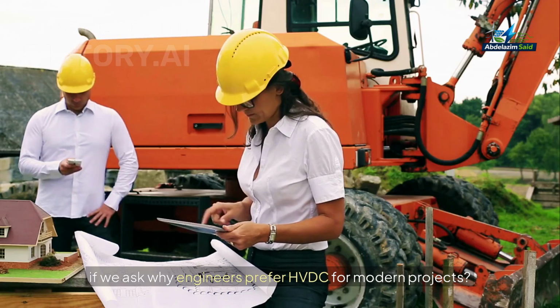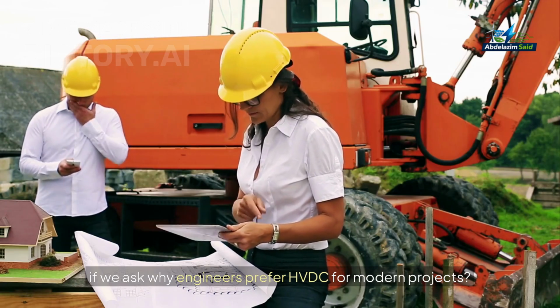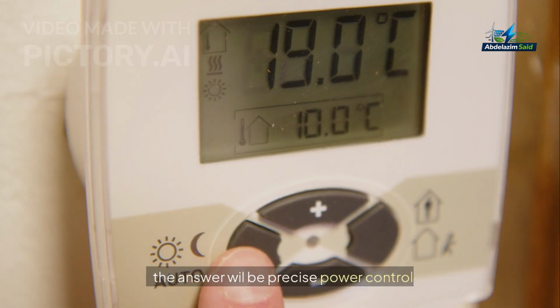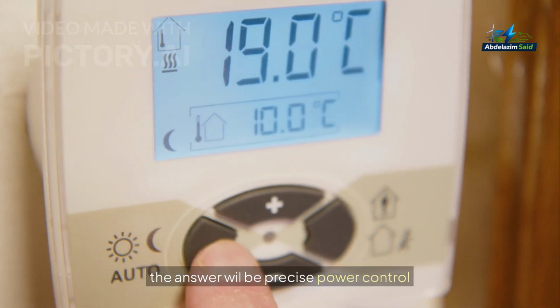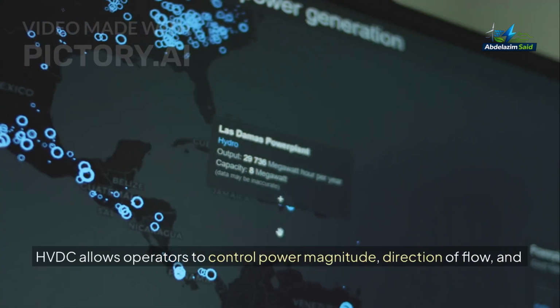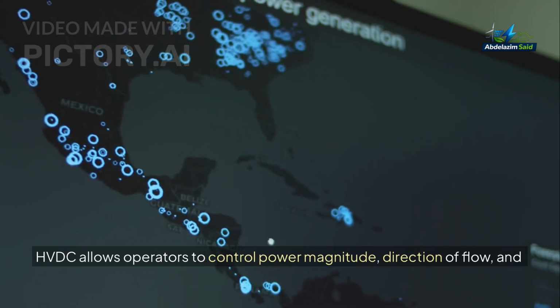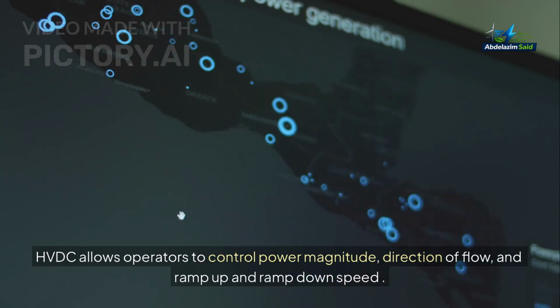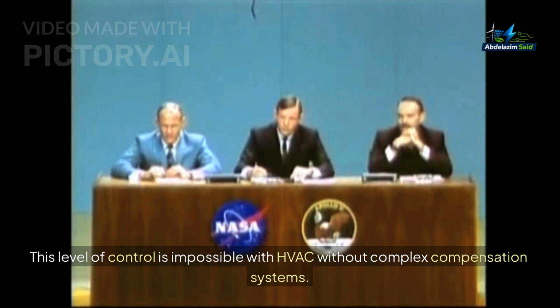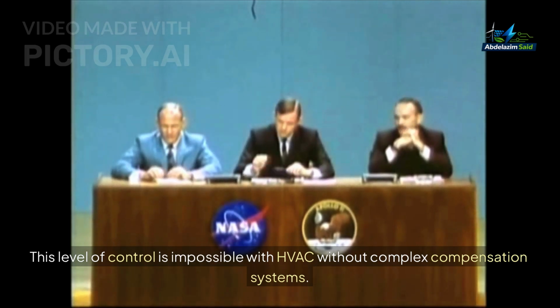If we ask why engineers prefer HVDC for modern projects, the answer is precise power control. HVDC allows operators to control power magnitude, direction of flow, and ramp up and ramp down speed. This level of control is impossible with HVAC without complex compensation systems.